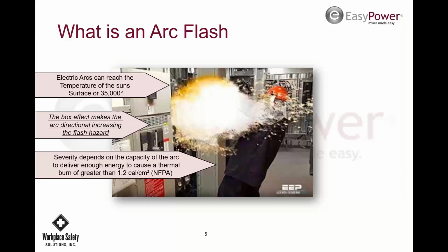So 1.2 calories, just to give you an idea of what heat it is: if you have a 1.1 calorie arc flash, and it goes bang, you're going to have like a sunburn on your face and on your hands. If it's a 1.3, bang, now you've got blisters. So we don't want to go there. We want to protect our employees to make sure that they don't get that level of arc flash. So that's an important number.